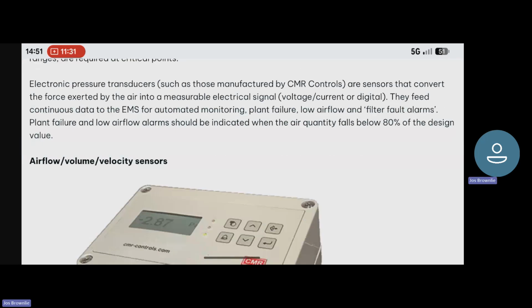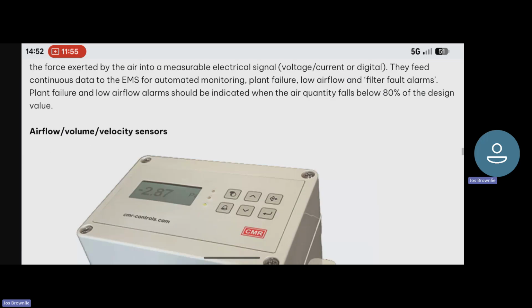Electronic pressure transducers, such as those manufactured by CMR Controls, are sensors that convert the force exerted by the air into measurable electrical signals, voltage and/or current and/or digital. They feed continuous data to the EMS for automated monitoring, plant failure, low airflow, and filter fault alarms. Plant failure and low airflow alarms should be indicated when the air quantity falls below 80% of the design value.